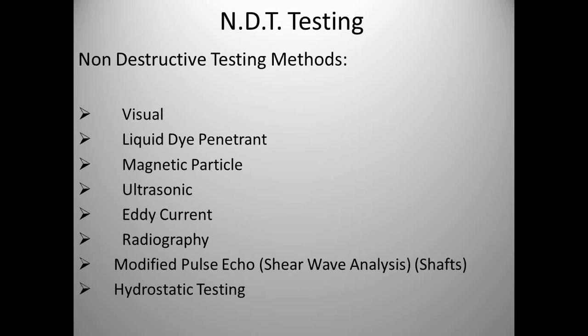For stationary equipment, non-destructive testing includes visual, liquid dye penetrant, magnetic particle, ultrasonic testing, eddy current, and radiography — a lot of different technologies to find failures. We find cracks in vessels, corroded welds, corroded tanks, and defective welds without good penetration. I was at an aluminum recycler a few weeks ago where they put liquid dye penetrant on all the lifting eyes of 17-ton ore pots every month looking for cracks — because you don't want to drop a 17-ton vat of molten aluminum, which could injure or kill people and damage a lot of equipment.